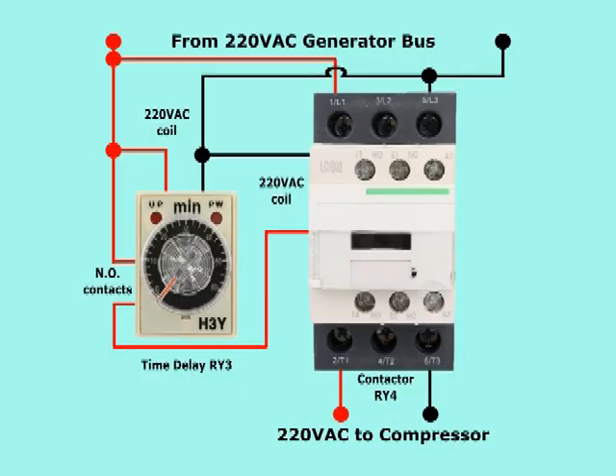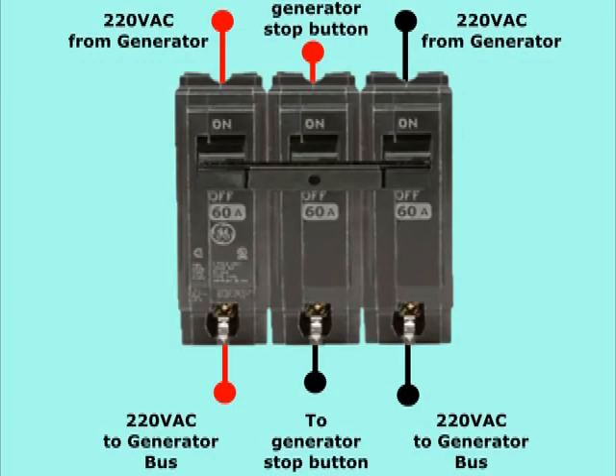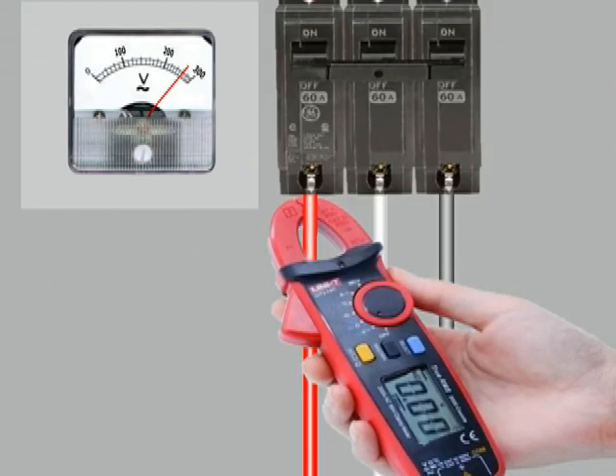On the other hand, we will see in more detail the way in which the time delay relays work on the generator bus, in order to fulfill their function of staggering the starting times of the various loads, so as to avoid overloading the generator when starting several loads at the same time. We will also see the addition of a 3-pole switch, which is used when for maintenance reasons it becomes necessary to start and stop the generator without interfering with the rest of the system.